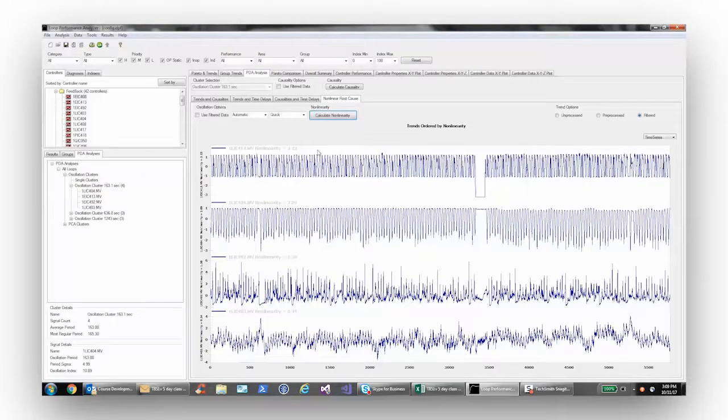The process may act as a filter. So, for example, if you have a square wave, as it moves through the process is typically going to filter it out, so it becomes more like a sine wave. That's an oversimplification, but in general, the more nonlinear the signal, the more likely it is to be upstream or a contributing factor rather than something that's being caused by something else.